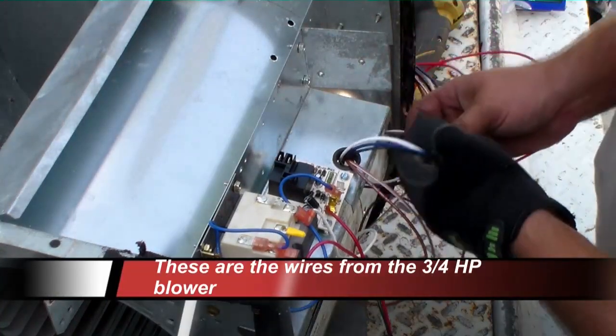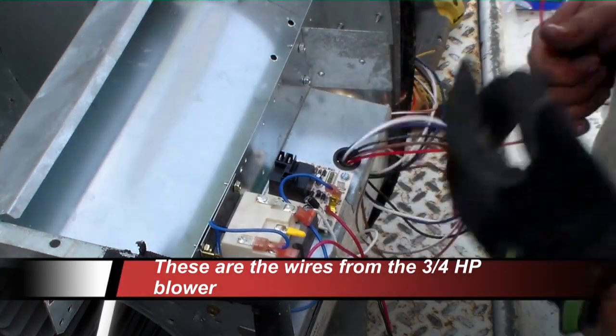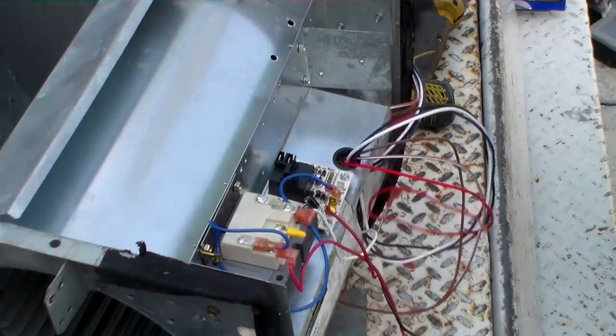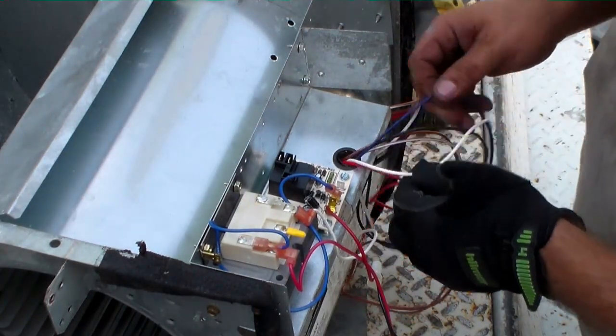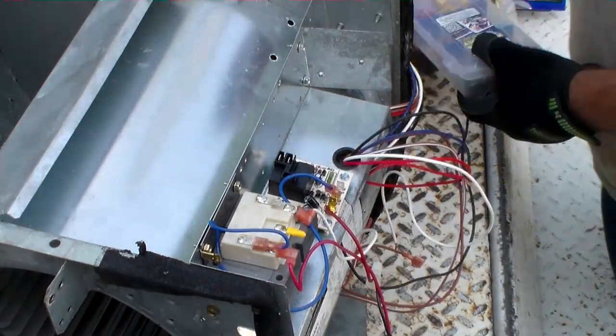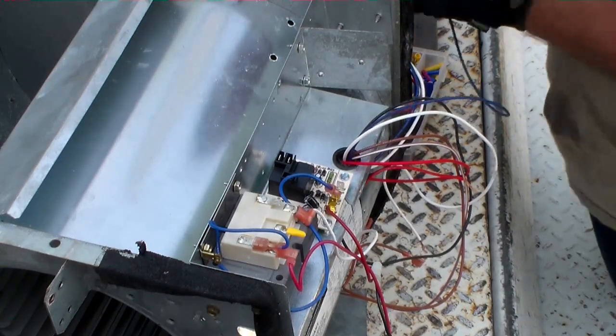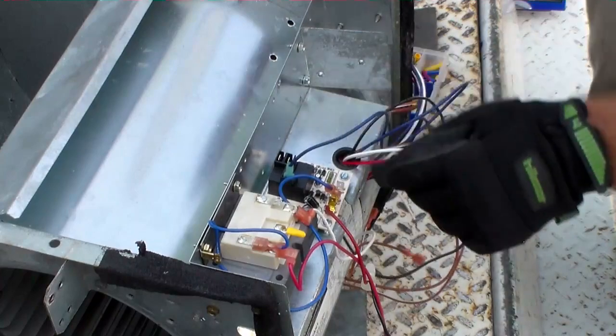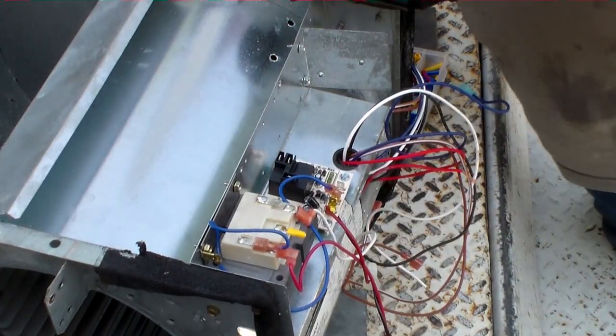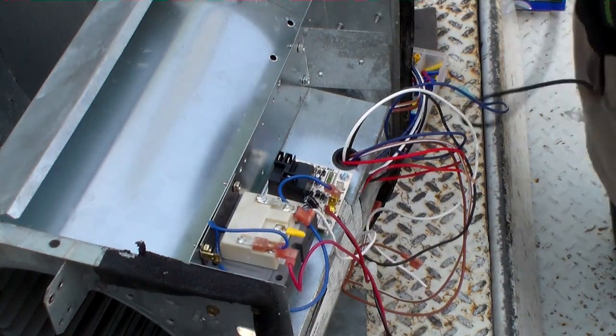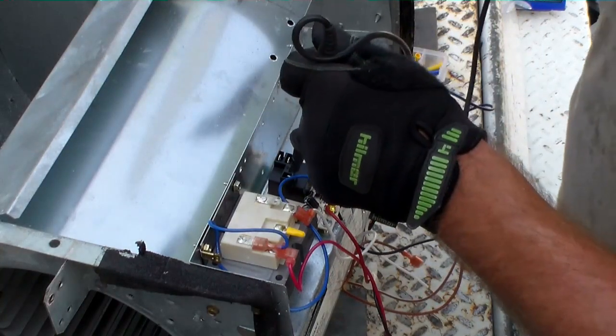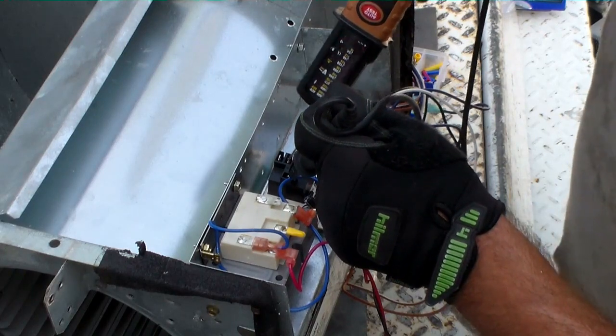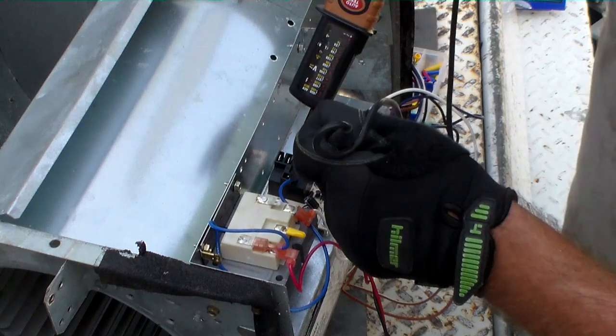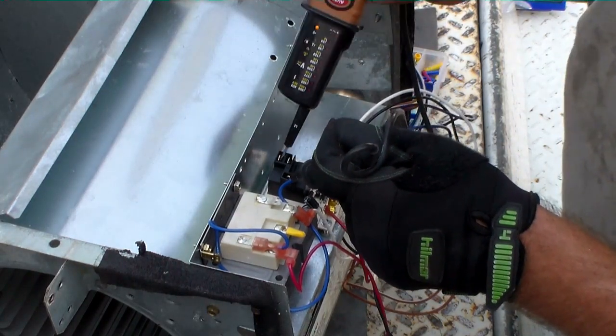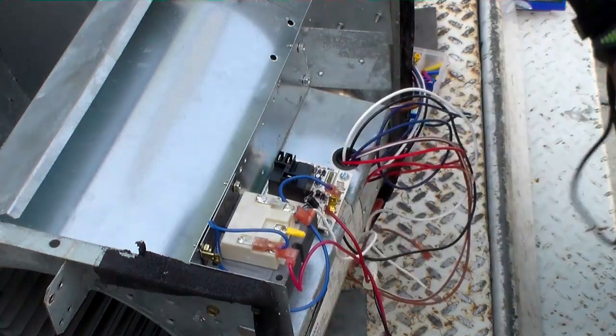Our white is one leg of our voltage. Red, blue, and black are the speeds. We'll go with medium first. Let's check them first to make sure. One will have continuity. These two should be open. And that will be our heat strip if we choose to do it that way. These two are open right now. These two are closed. Go into the heat strip to the blower.